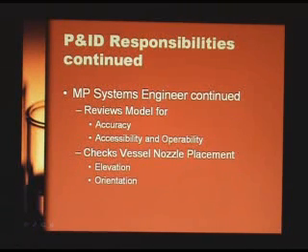It might not be placed correctly in relationship to some temperature gauge. If the stream is coming in, you want to be able to read that temperature, so you want the two of them to be close together rather than the opposite side where the temperature will not be read. So anytime we have a model, the process engineer is going to be looking for these things and making sure that the process will operate, that the data that the operator needs will be there.